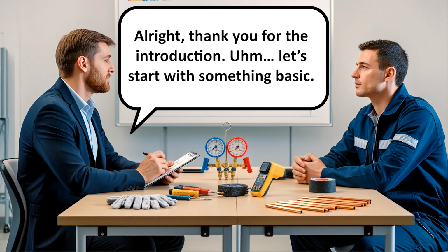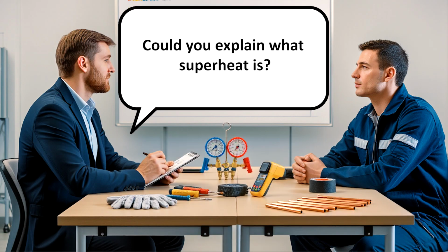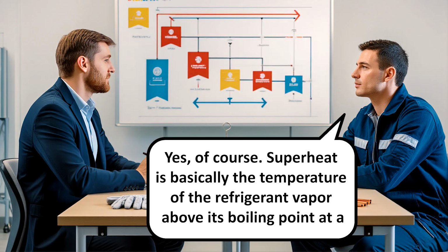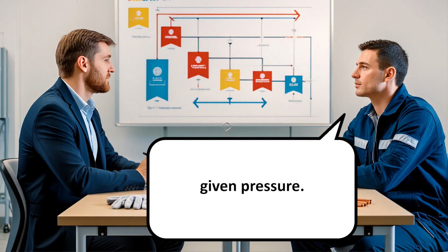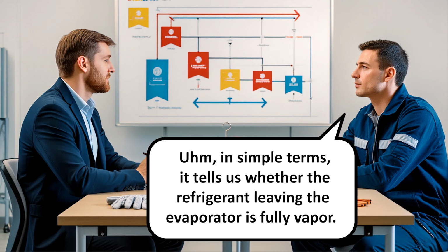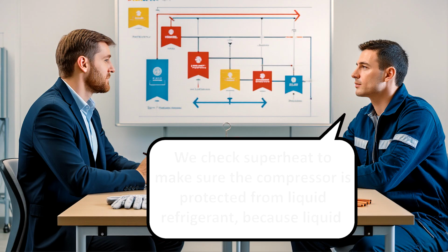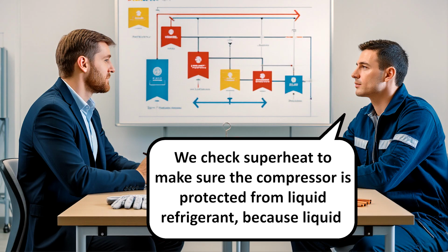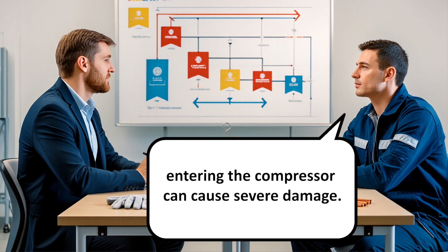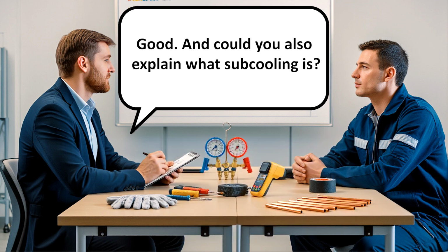All right, thank you for the introduction. Let's start with something basic. Could you explain what superheat is? Yes, of course. Superheat is basically the temperature of the refrigerant vapor above its boiling point at a given pressure. In simple terms, it tells us whether the refrigerant leaving the evaporator is fully vapor. We check superheat to make sure the compressor is protected from liquid refrigerant because liquid entering the compressor can cause severe damage.